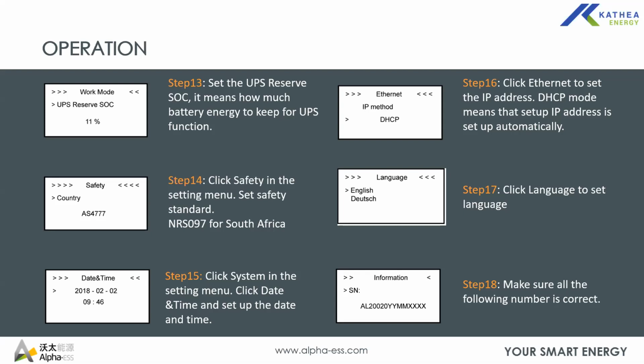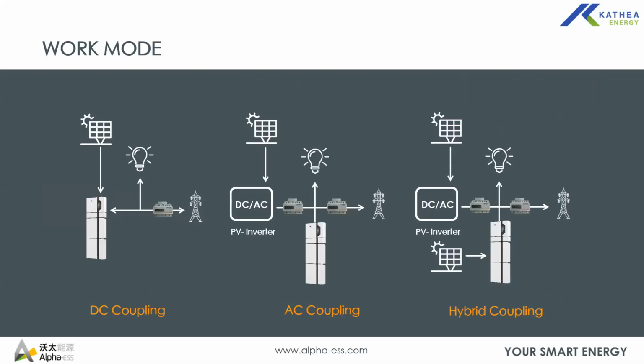So we'll quickly go through the work modes. As I said earlier, the normal setup is where you have your PV to the system, you have your battery, you have your loads, and then you have your grid. It's a DC coupling system. So on system mode, you need to set it to DC.